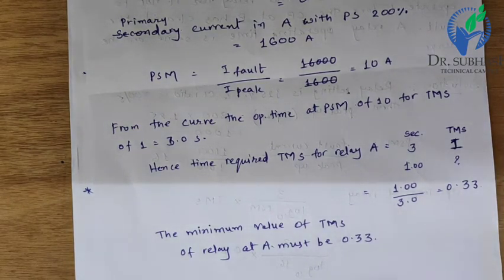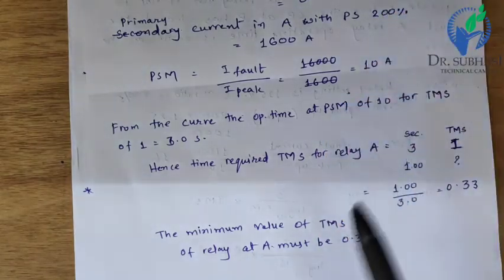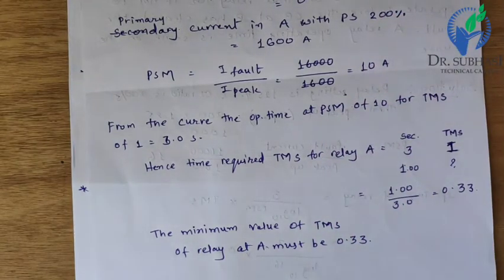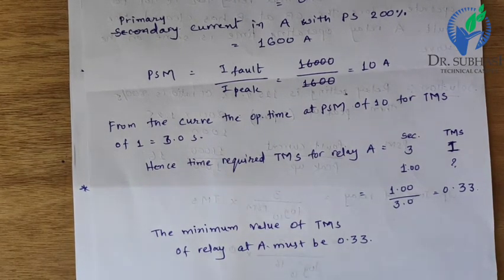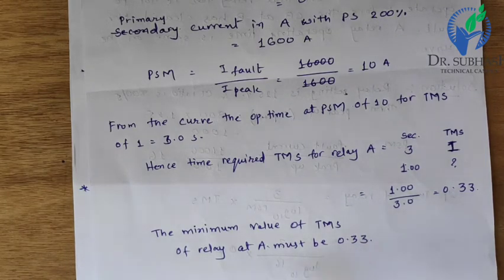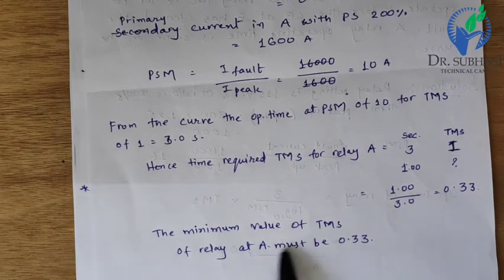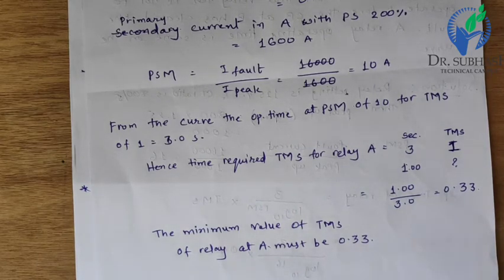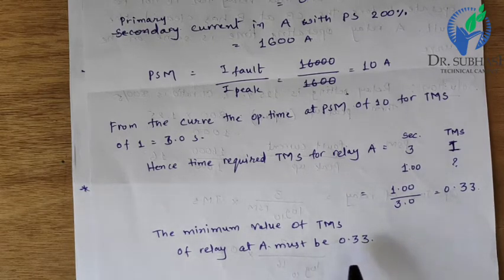In conclusion, relay B will operate in 0.5 seconds and after the discrimination time, relay A will reset. If relay B does not operate due to malfunctioning, relay A will operate after the discrimination time, giving relay A an operating time of 1 second with TMS of 0.33.